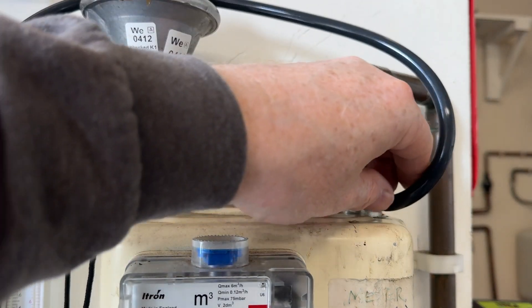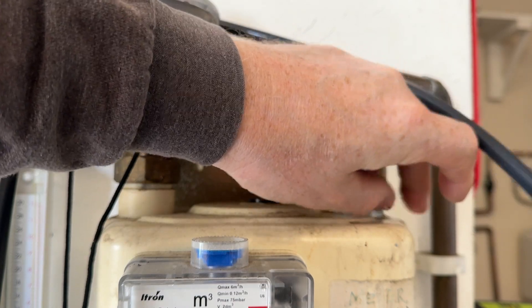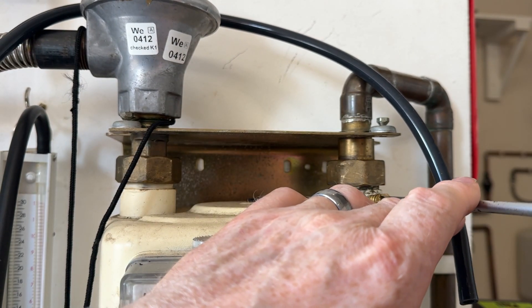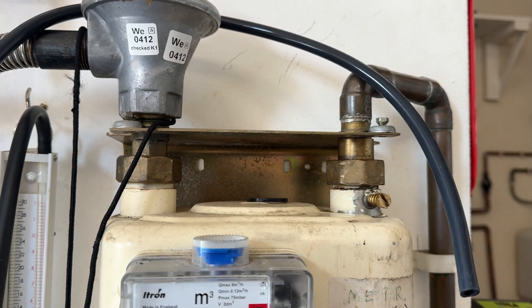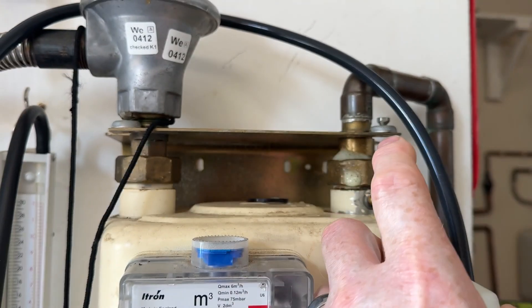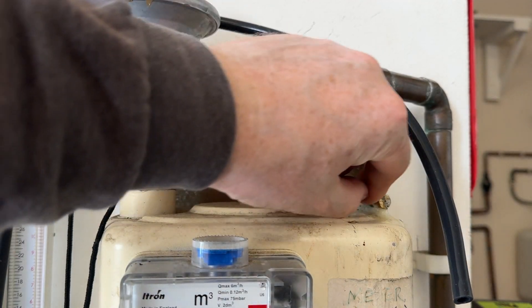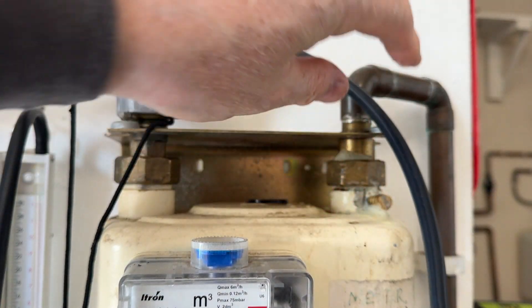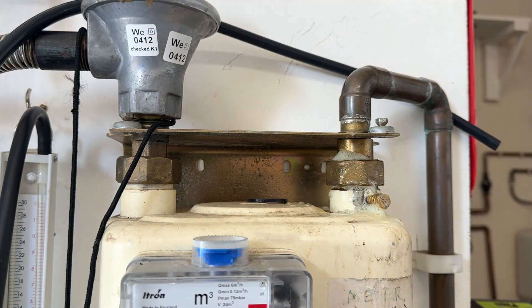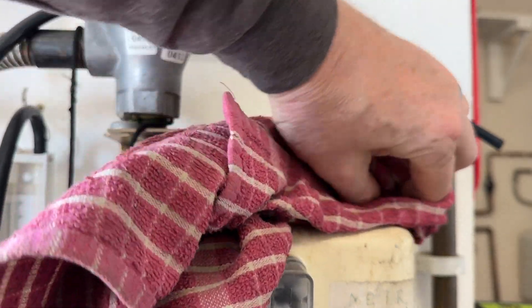We can now disconnect our hose and replace our test nipple. Again, using our flat screwdriver, make sure we don't over tighten it. We can now turn on the gas supply and then we can test whether the test nipple is leaking by using our leak detection fluid, commonly known as LDF. Wait for a few seconds to make sure it's not leaking, and then using a nice clean cloth, we can now remove the excess LDF so it won't corrode the gas meter.